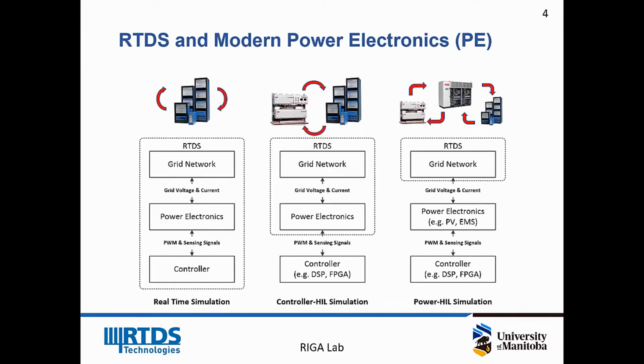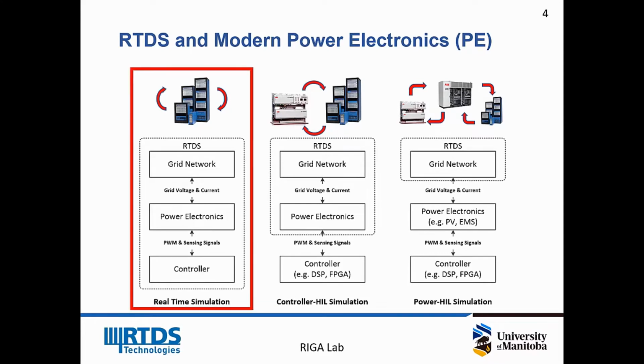Modern power electronic systems are getting popular in power system applications. For example, solar energy requires a PV inverter to inject power to the grid network. If scientists, researchers, or engineers want to simulate a power electronic system with a power system network in real time, we can use a real-time simulator to model the power electronic systems and the network. All the models run inside the real-time simulator.